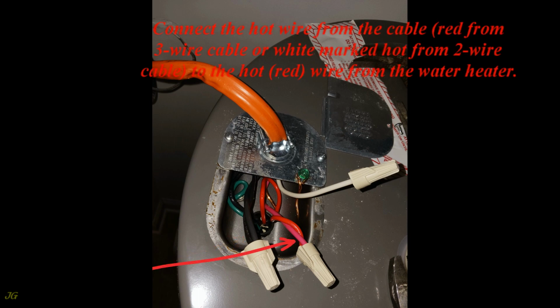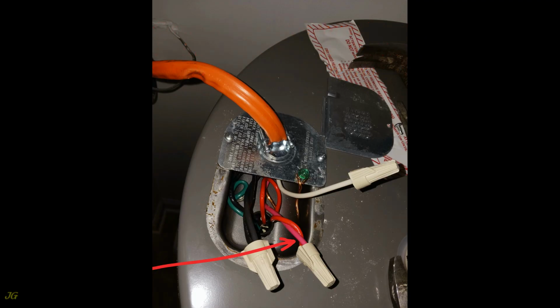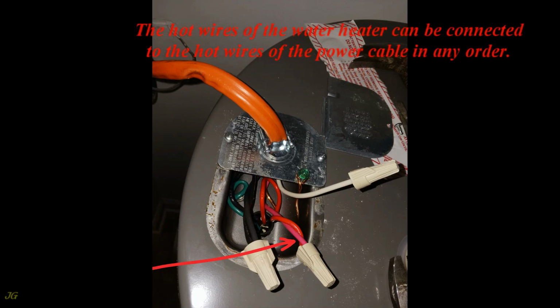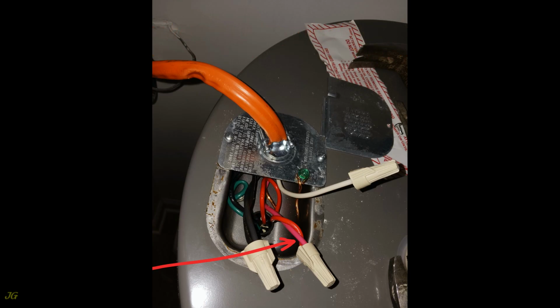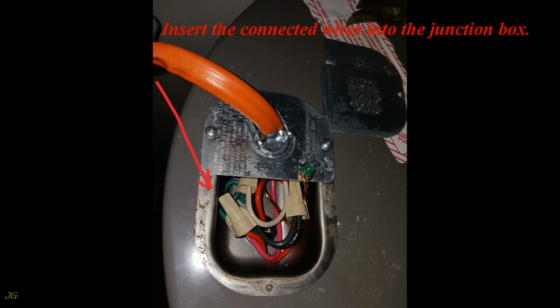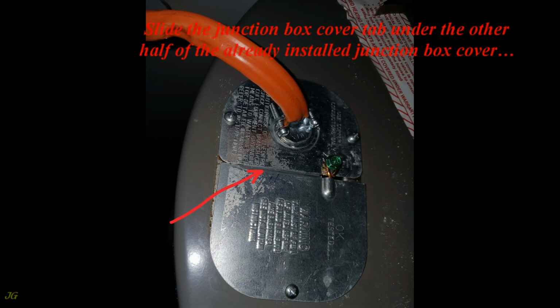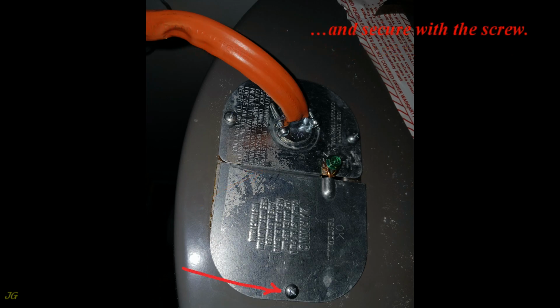Connect the hot wire from the cable, red from 3-wire cable or white marked hot from 2-wire cable, to the hot, red wire from the water heater. The hot wires of the water heater can be connected to the hot wires of the power cable in any order. Insert the connected wires into the junction box. Slide the junction box cover tab under the other half of the already installed junction box cover and secure with the screw.